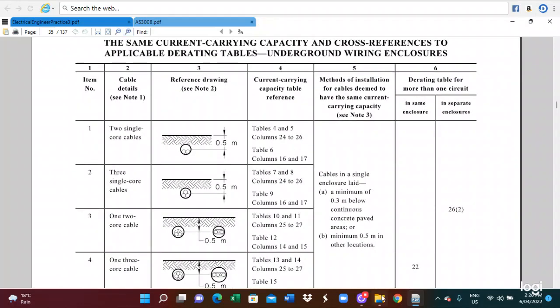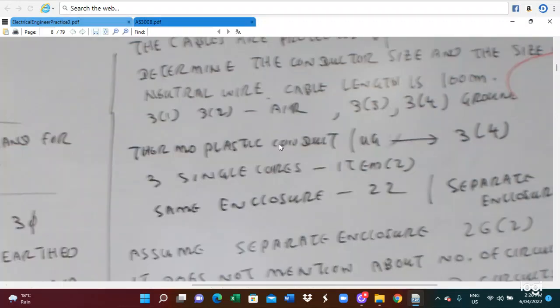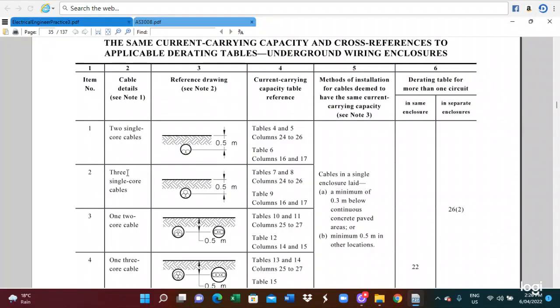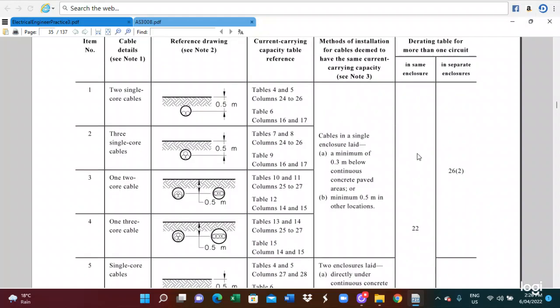Okay, so this is an underground enclosure, and then we look at item 2, 3 single core cable. This is single core cable, this is item 2. In this case, we have to refer to table 7, 8 or 9: table 7 for V75, table 8 for V90, and table 9 for V110. Also, for derating we have to use the same enclosure derating table, which is table 22. Those have to be utilized.